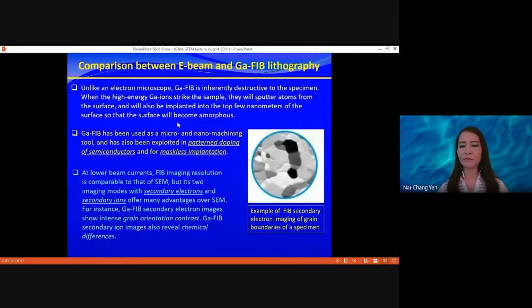Your surface often becomes amorphous because you really damage the surface, since these ions are heavy. But they've been used effectively to remove materials. You can also dope the material or do maskless implantation of ions. But if you use a much lower beam current, you can do imaging, and the imaging resolution is similar to scanning electron microscopy.